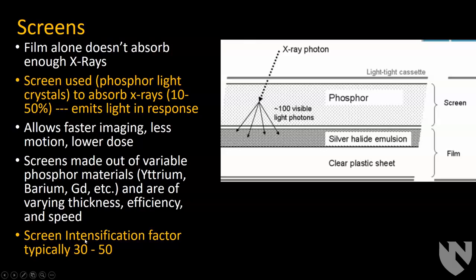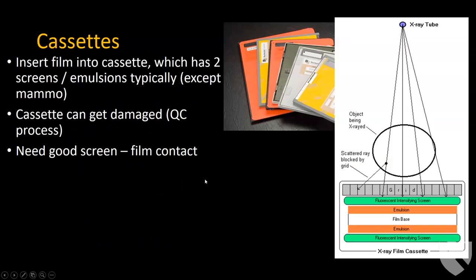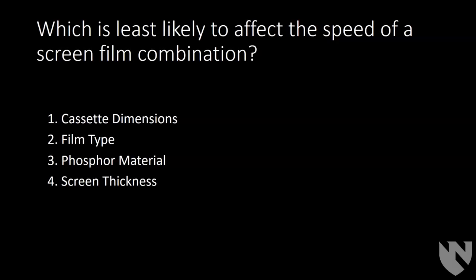Cassettes are basically the name of the whole assembled process: a film inserted in a cassette with two screens. The exception is mammography, which has one screen for higher resolution. Cassettes can get damaged — you can break the screens — so you need to do QC on them. You also need to ensure good screen-to-film contact for proper light transfer. The next question: what is least likely to affect the speed of a screen-film combination? The answer is cassette dimensions. The size of the cassette doesn't affect how long you need to expose it.